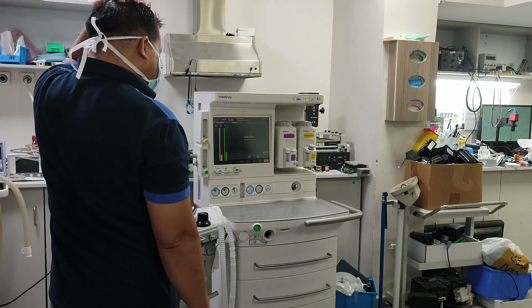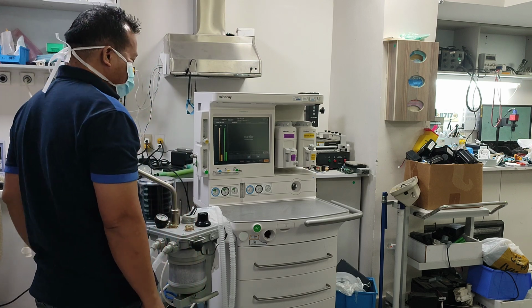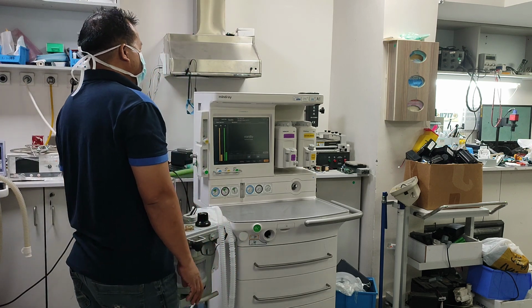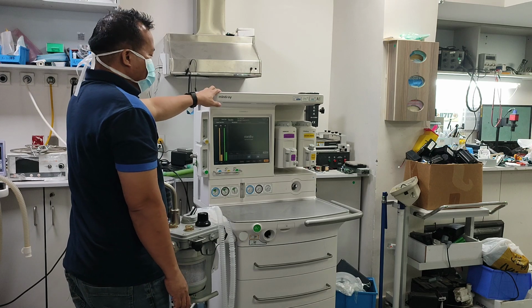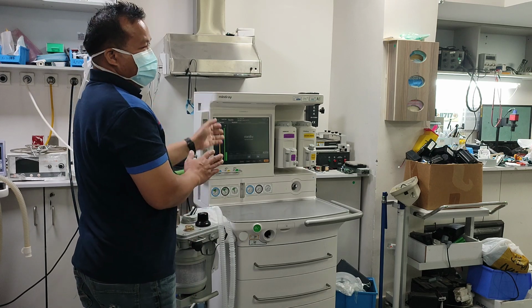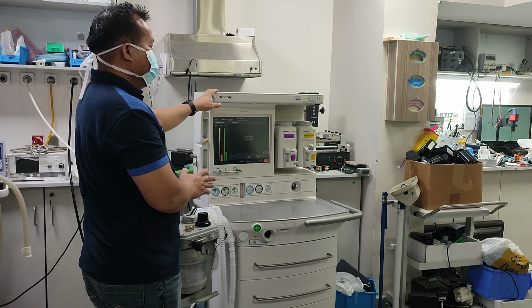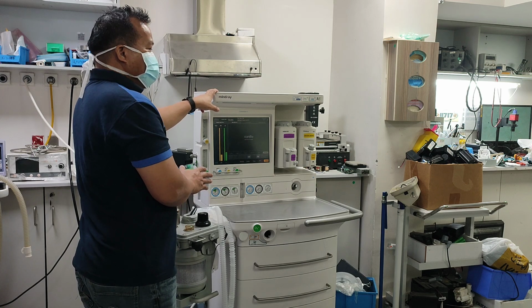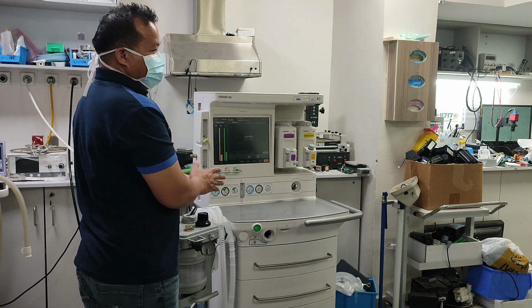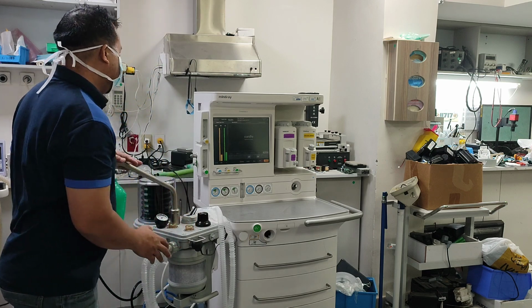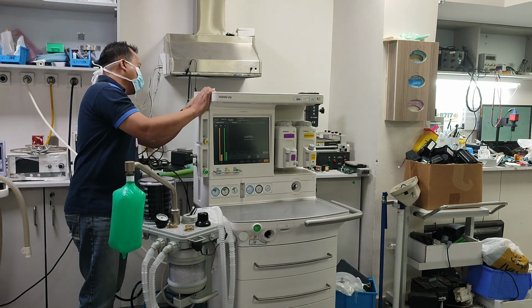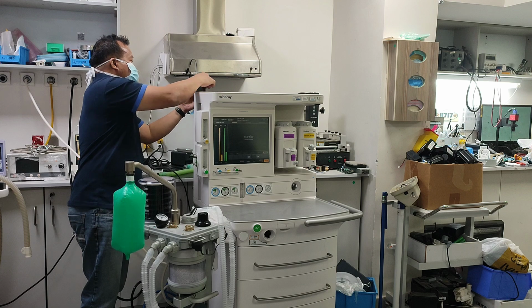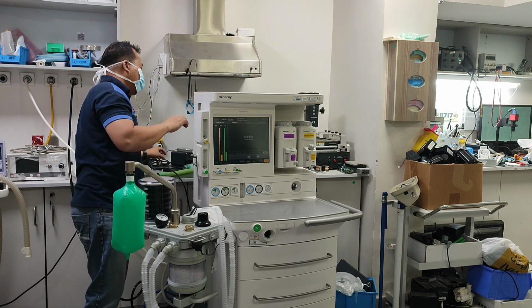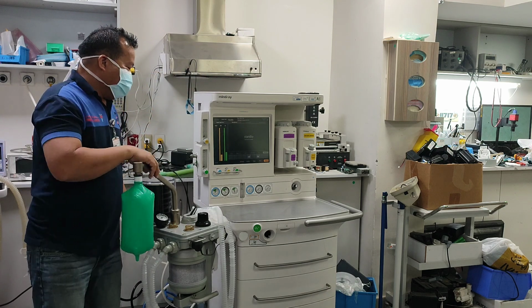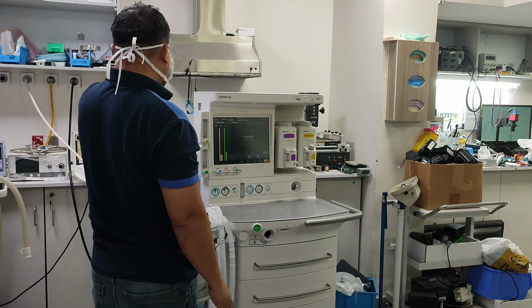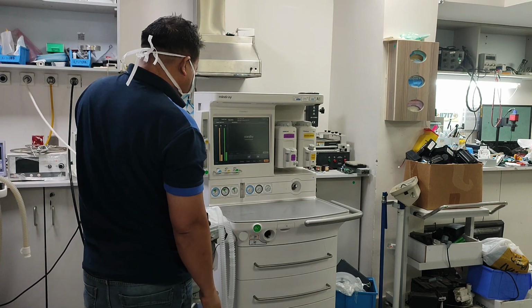So here we have biomed maintenance for this one every 6 months. The purpose of the maintenance is to prolong the life of the machine. Every 6 months you will change some parts, for example, the dust filter. Here there is a dust filter we need to change. If you do not change it, it will block, and it will damage the components inside. So you should change the filter.